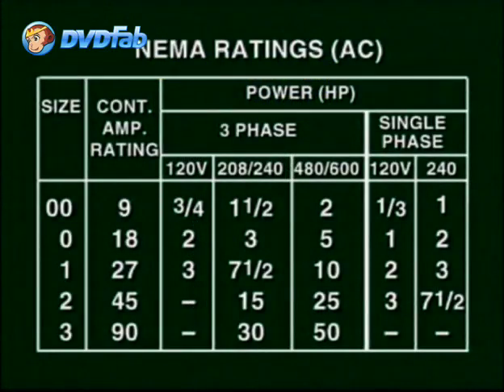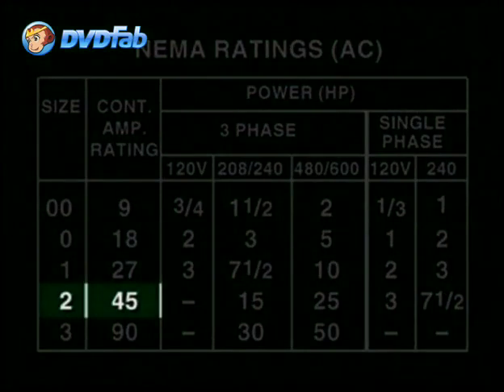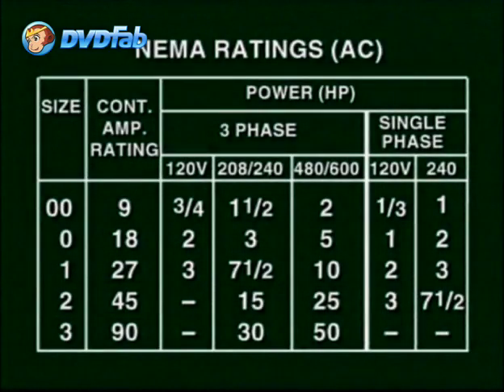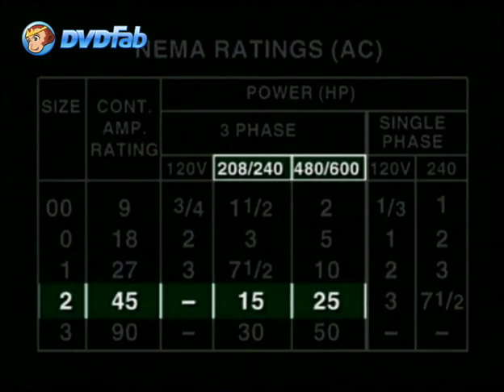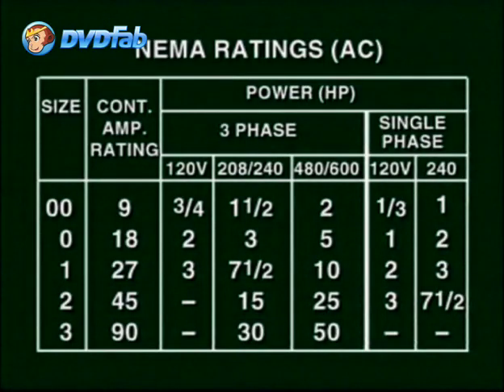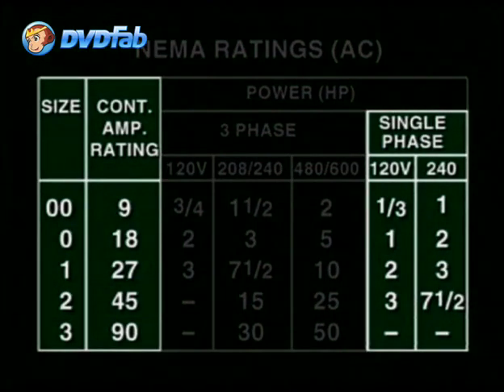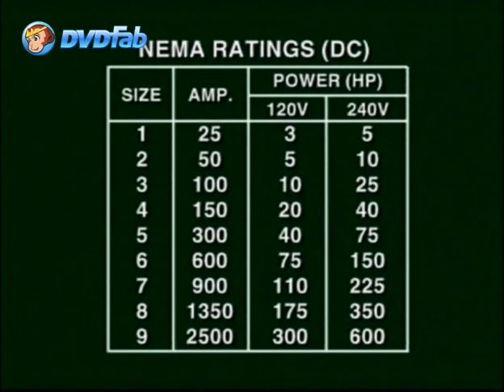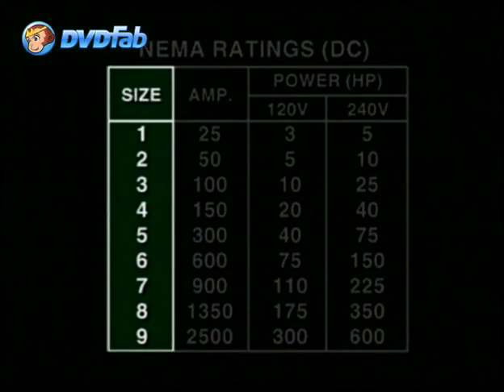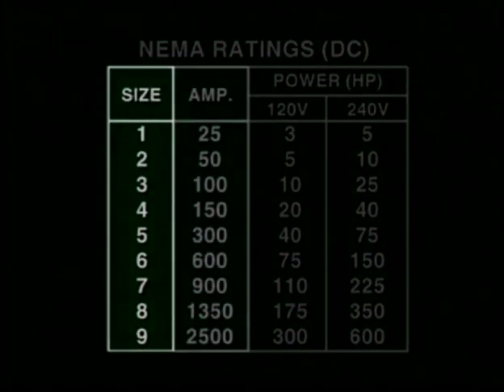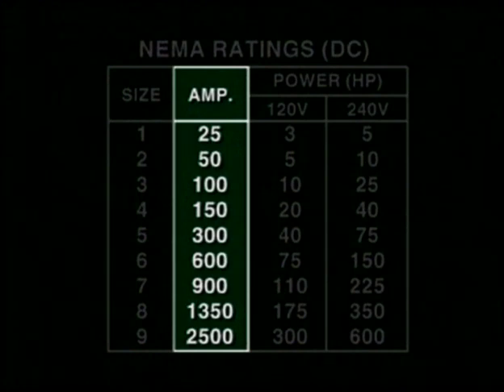For example, a NEMA 2 contactor is used when you need up to 45 amps continuous current. This contactor could be used in a 15 or 25 horsepower load application of a 208, 240 or 480 volt system, respectively. The single-phase NEMA 00, 0, 1, and 2 ratings are only available to 120 and 240 volt systems from 1/3 to 7.5 horsepower. The standard rating available for DC contactors are from size 1 to 9, with current capacities ranging from 25 amps to 2500 amps.